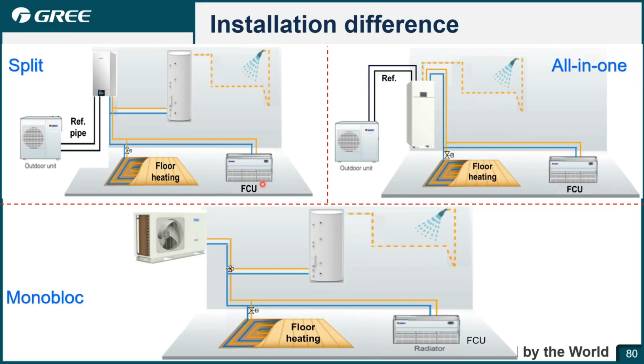And for the installation difference, here is a split. So for the project, you need to do the brazing, the copper pipe connection, and the water pipe connection between the hydro box and the water tank, and the hydro box to the floor heating and FCU, right? However, for the all-in-one, we also need the copper pipe installation. However, no need to connect the hydro box and water tank.